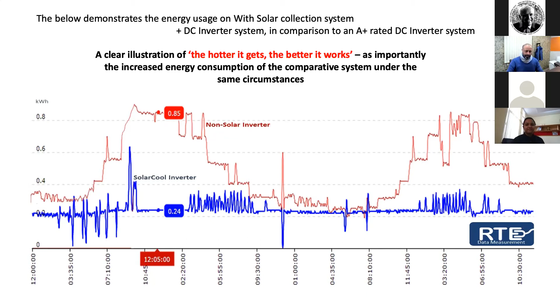How does it help in addition to energy saving? It helps in terms of saving the compressor from mechanical damage. The moment something is working mechanically, it will have a kind of resistance and wear and tear. Continuous spiking will cause more wear and tear compared to having a constant speed on the compressor. So this is also one of the additional benefits which comes as a package with hybrid conditioning.